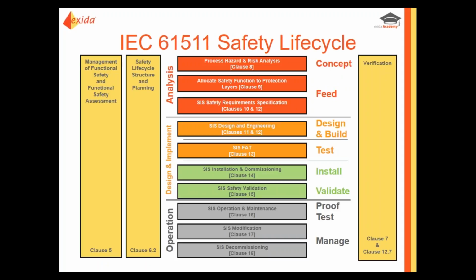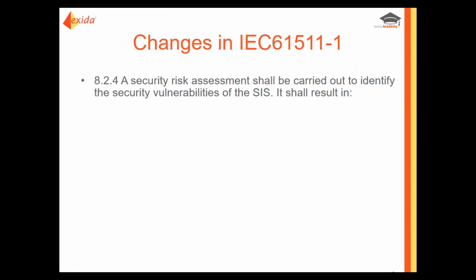So if we look at the life cycle, the first thing we do is process hazard and risk analysis. This is where 1511 has been changed. 1511 now has a new clause to cover cybersecurity. So what 1511 now says is that you need to carry out a security risk assessment to identify your security vulnerabilities.